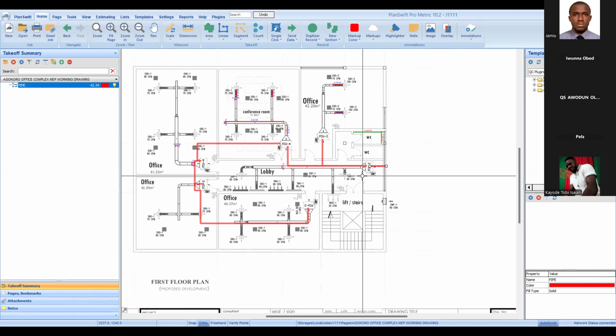Let's not forget, at every interval of your pipe you have something called a joining coupler. In electrical we call it a coupler, in mechanical we call it a socket. All this will be built into your build-up rate for your conduit pipe, because I can't just say I want to use 10 numbers of joining coupler. In your build-up rate, you factor it in that for every so many meters, you'll use so many couplers.